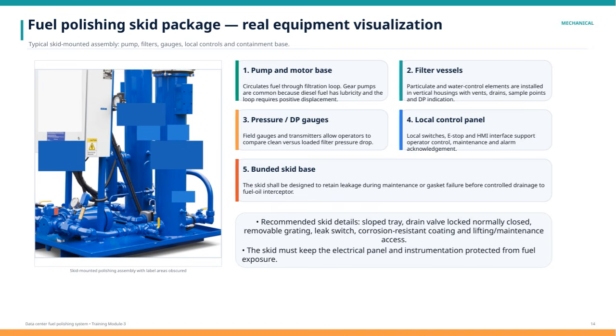The bund skid base is designed for safety. It retains any leakage during maintenance or gasket failure, preventing environmental contamination by directing fuel to a controlled drainage system. Additionally, recommended skid details include features like a slope tray, a drain valve that remains normally closed and locked, removable grating, leak detection switches, corrosion-resistant coating, and easy lifting or maintenance access. It's also critical that the skid design keeps the electrical panel and instrumentation well protected from fuel exposure to ensure reliability and safety. Overall, this well-thought-out skid assembly is key to effective and safe fuel polishing operations.